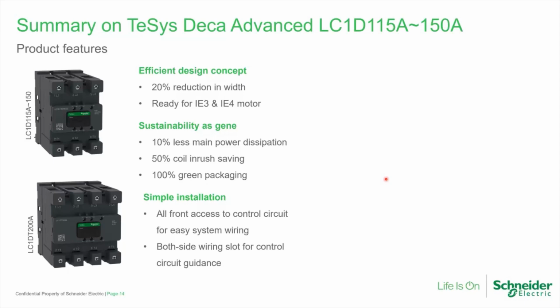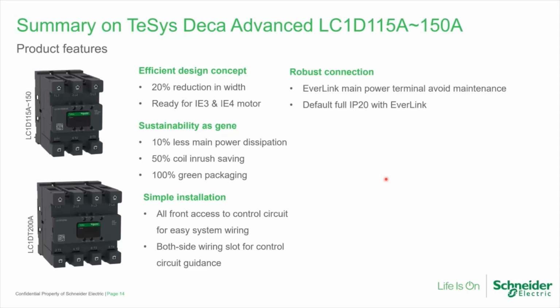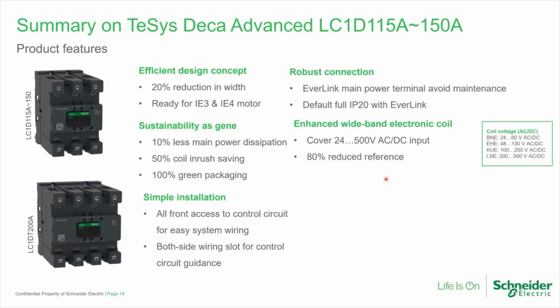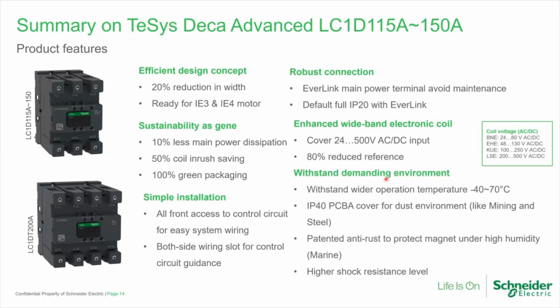As we mentioned, it is simple in installation: all the connections are given front access, and there are both side wiring slots for control circuit guidance. It is extremely robust as we are offering these contactors with Everlink main power terminals, and by default these Everlink contacts come with full IP20. Wideband electronic coils are offered so that the entire range from 24 to 500 volt AC/DC is covered. Existing contactors have 225 references. With this contactor, all those 225 references are reduced to only 24 references, and hence we are saying that 80% of references are reduced.